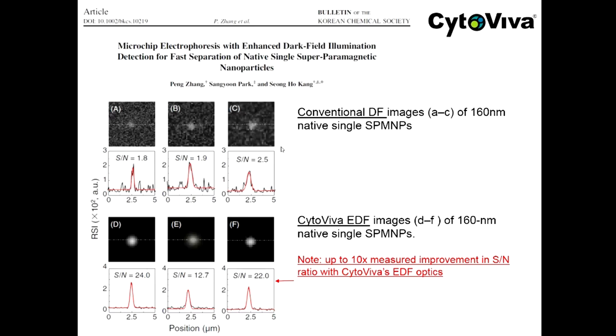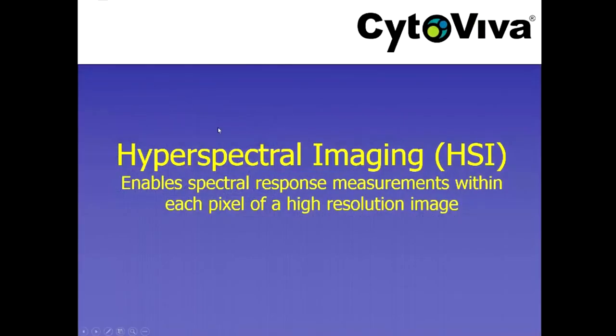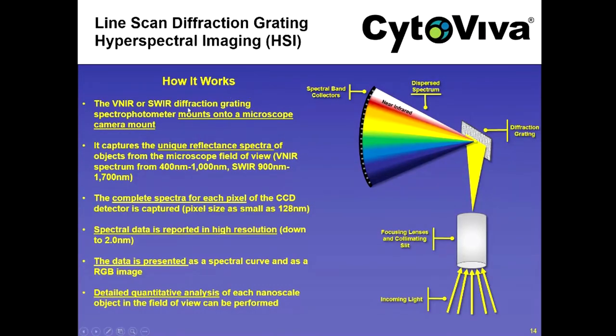That Korean research group took quantitative measurements comparing an identical particle using standard dark field versus CytoViva enhanced dark field. They were able to quantitatively measure about a 10x increase in signal-to-noise ratio versus off-the-shelf dark field optics from Olympus, Nikon, or Zeiss. This third-party validation demonstrates how well these enhanced dark field optics work compared to standard dark field optics.